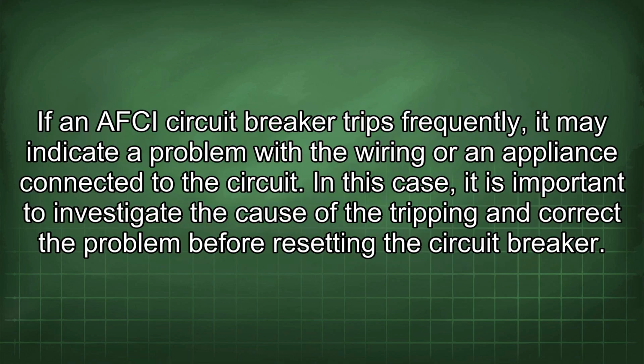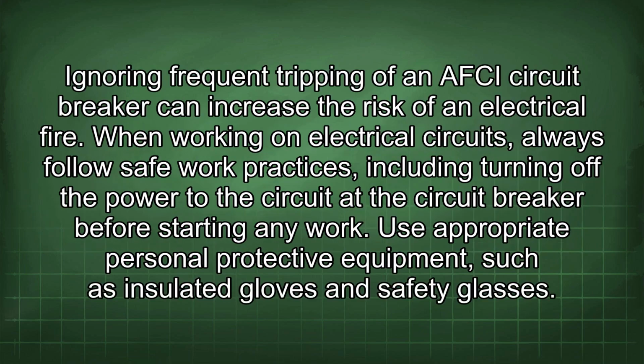If an AFCI circuit breaker trips frequently, it may indicate a problem with the wiring or an appliance connected to the circuit. In this case, it is important to investigate the cause of the tripping and correct the problem before resetting the circuit breaker. Ignoring frequent tripping of an AFCI circuit breaker can increase the risk of an electrical fire. When working on electrical circuits, always follow safe work practices, including turning off the power to the circuit at the circuit breaker before starting any work.